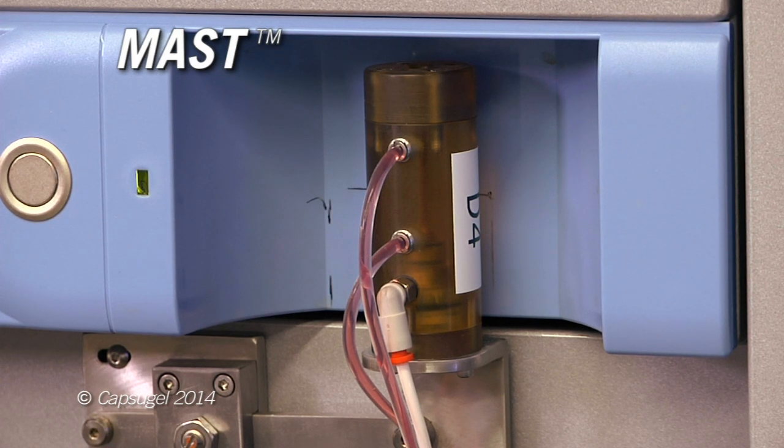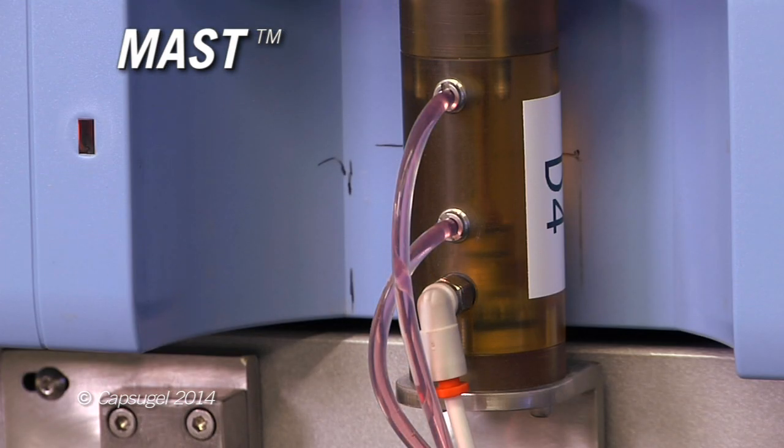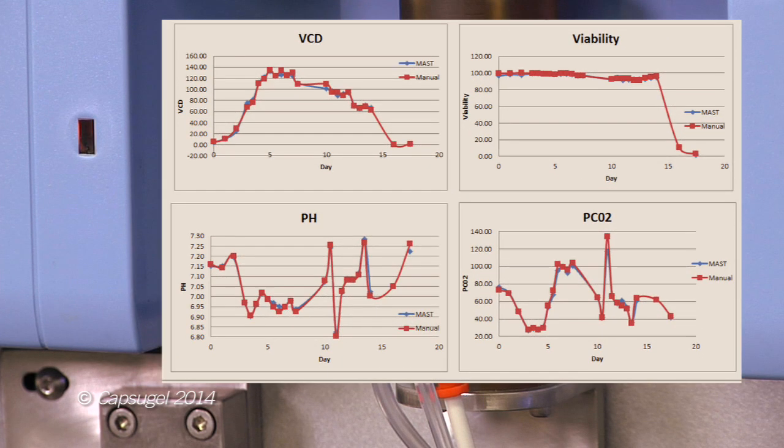Multiple units have been installed at client facilities. Automated sampling to the NOVA has been repeatedly demonstrated at Pfizer and in-house to be consistent with manual sampling. Viable cell density as well as viability are very consistent. The pH between MAST and manual is virtually identical, as is dissolved carbon dioxide.